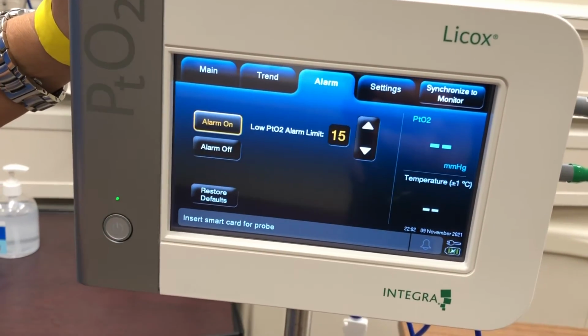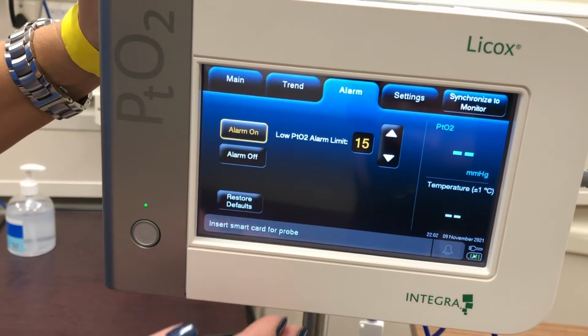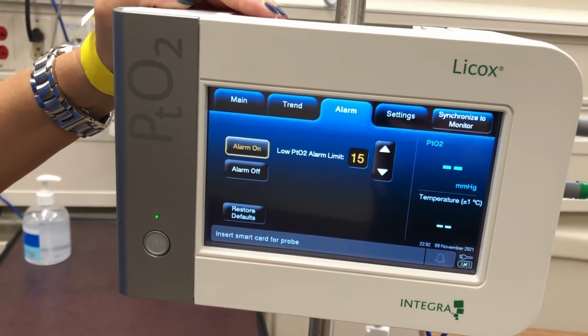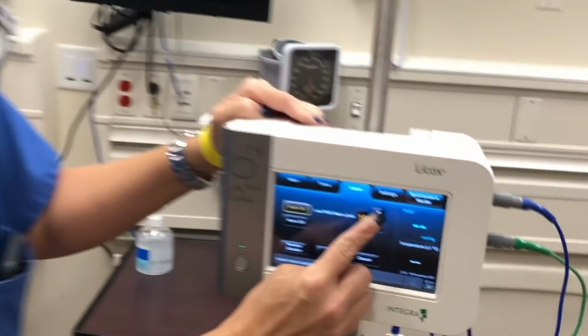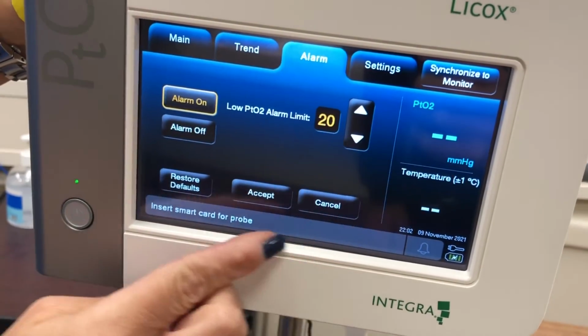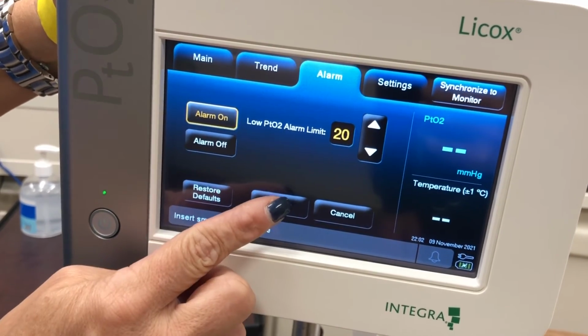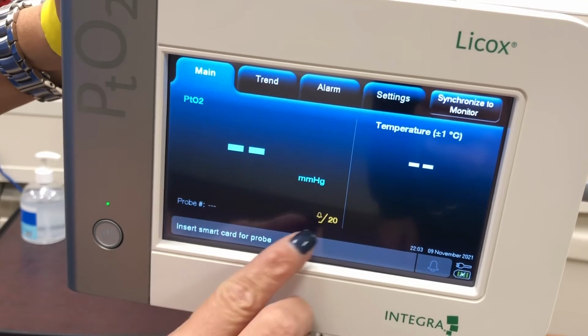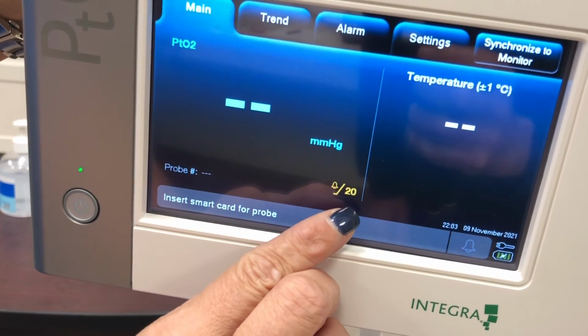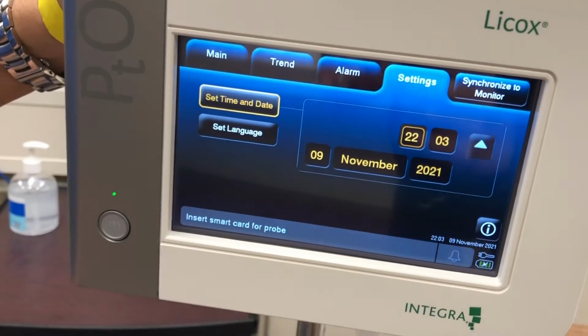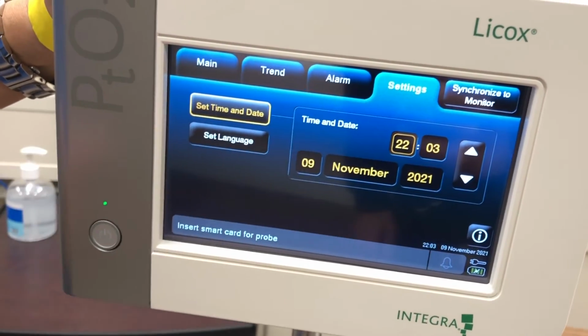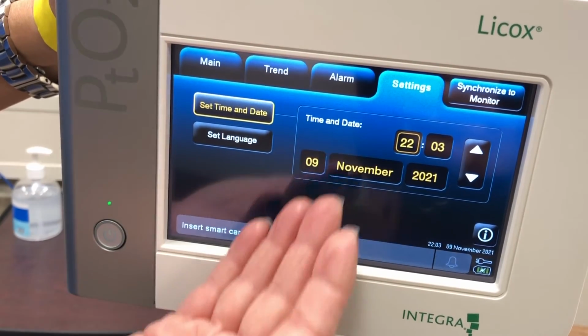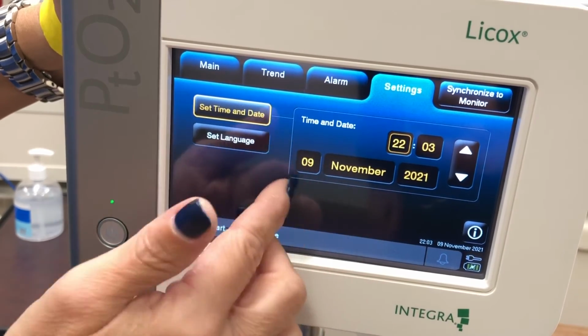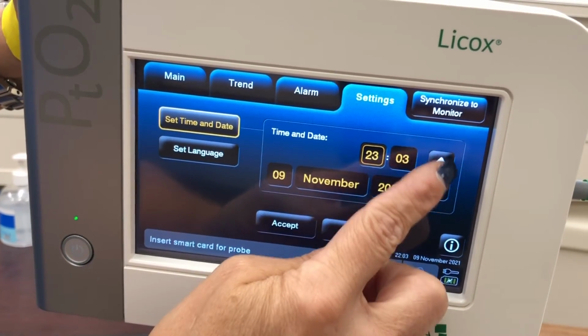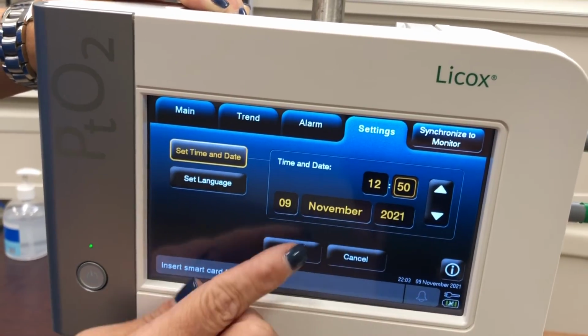The next tab is the alarm tab. Remember I was telling you that the default is 15. Most of the algorithms being utilized by neurointensive care these days treat if less than 20. So I would go here and put the arrow up till I got 20. I'm always going to be told what to do here. I need to accept it. So I hit accept, and now you see I'm back on that main screen. You see the alarm bell, and it's over 20 because I've changed the default. Settings: just as it would note, it would be the time and the date change, the language change, all of those. Right now, it looks like we're at 10 o'clock at night, but it is November the 9th, which is correct. So I hit accept.